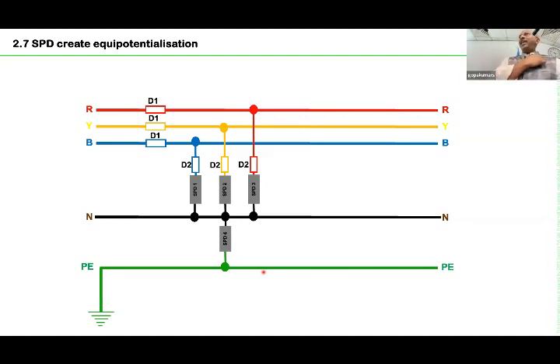Now imagine there is a lightning strike, and as a result of the lightning strike, the ground potential is increasing. Lightning and ground potential are big subjects, probably we will talk about them another time. So because of the lightning, the ground potential is increasing. I am just connecting this green wire to red because suddenly, due to lightning, the potential of that particular wire is going very high. And how does the SPD operate? In normal condition, the internal resistance of the SPD is very high. But once the voltage between the terminals is more, suddenly it makes, imagine, a short circuit. Just for the time being, it's making a short circuit.